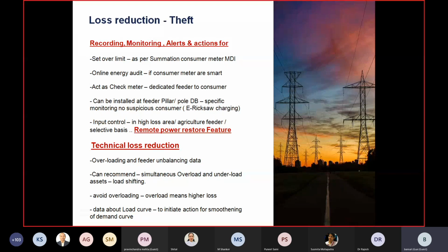We tried this in an area where there was a lot of theft. What we did was sum the total MDI and set that value, since consumers bypassing energy weren't being recorded in the MDI. So there was a limit set, and if anybody drew power by direct hooking, the ACB would immediately trip.